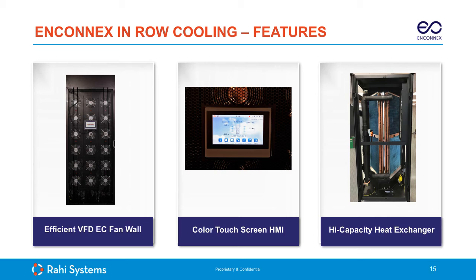So the Enconnex IRC was designed from the ground up, in partnership with Rahi Systems, to address the trends for the next generation data centers. It's well instrumented with predictive controls. It can handle the high density heat loads and the variable density heat loads. It has a clean design, and it looks like a server rack, and from the front, you just walk right past it. It's fully integrated controls, and it's got a human machine interface, an HMI, with a modern color touchscreen display. It can handle heat loads up to 100 kW per system in a comparatively small footprint, which is pretty impressive. So let's go to the next slide.